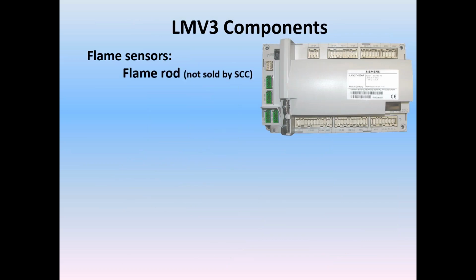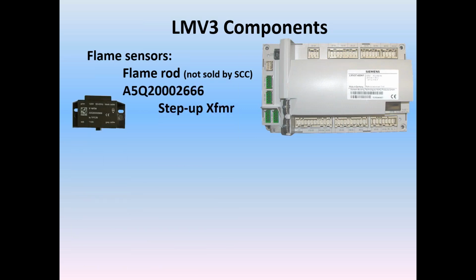For flame sensors, every flame safeguard that Siemens has made and most other makes have flame rods. SCC doesn't sell flame rods. They're usually very specific and custom in OEMs and very simple to make. So you can use a flame rod with an LMV3. And then on the flame rod, if you want, you can add the step-up transformer, to elevate the flame rod signal. This makes the flame rod more sensitive to the flame signal, more or less like an amplifier. The higher the voltage on the flame rod, the better the pickup of the flame presence.